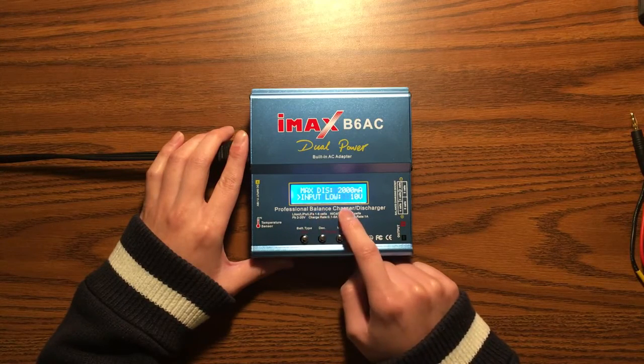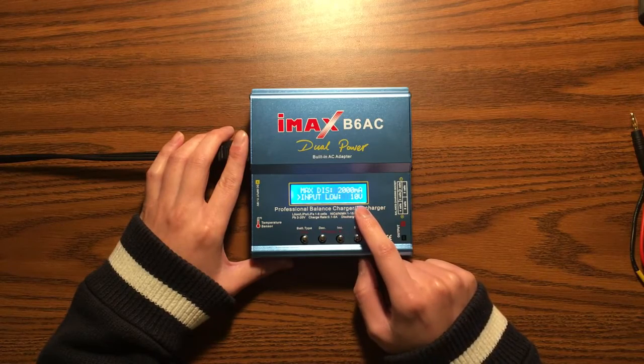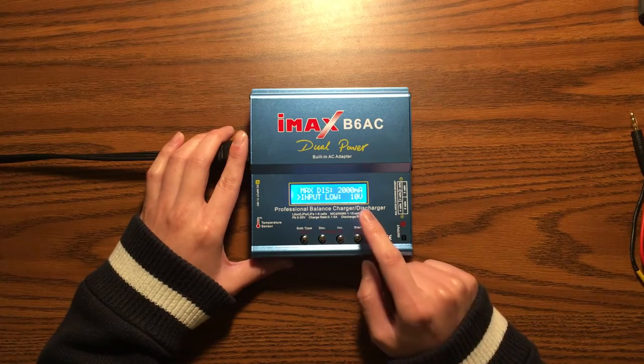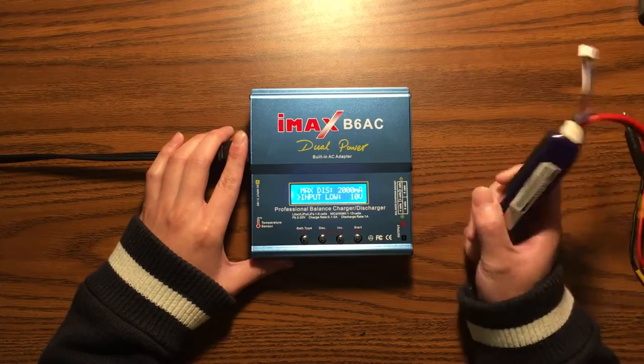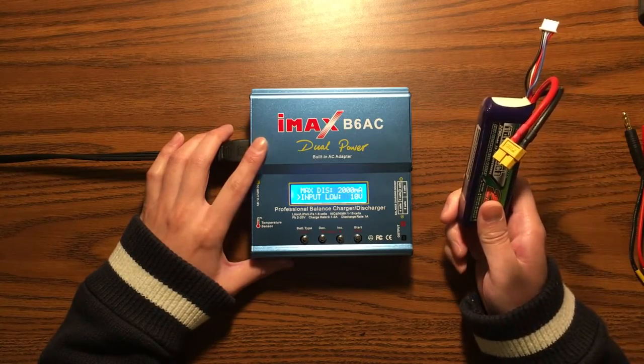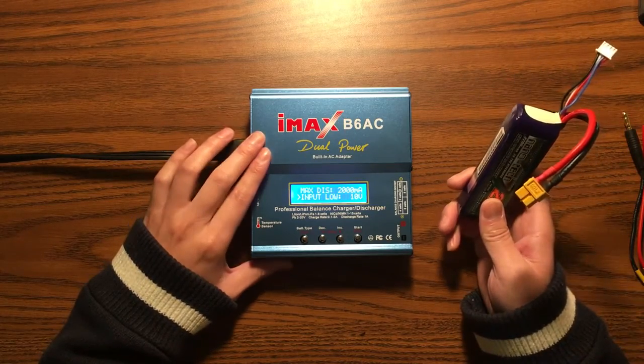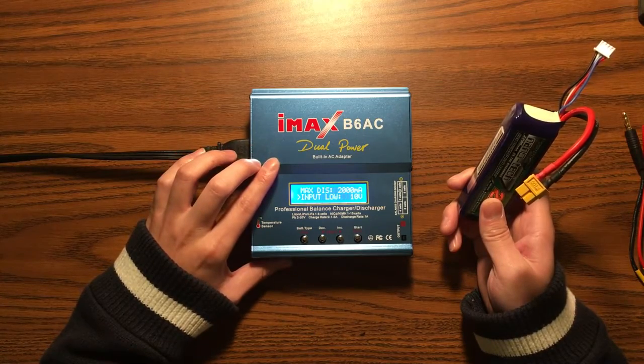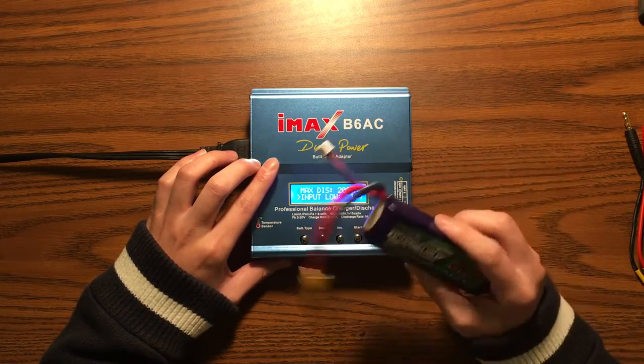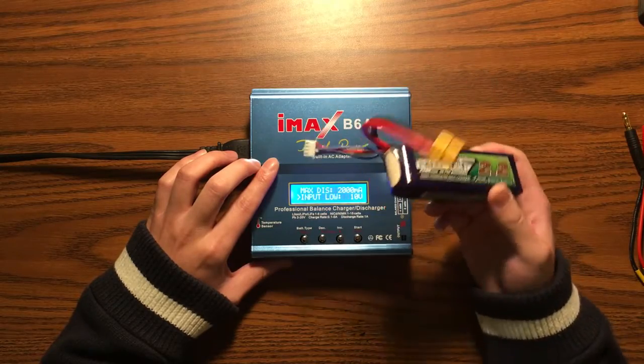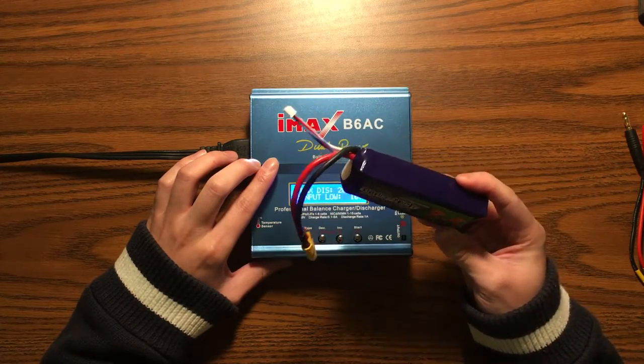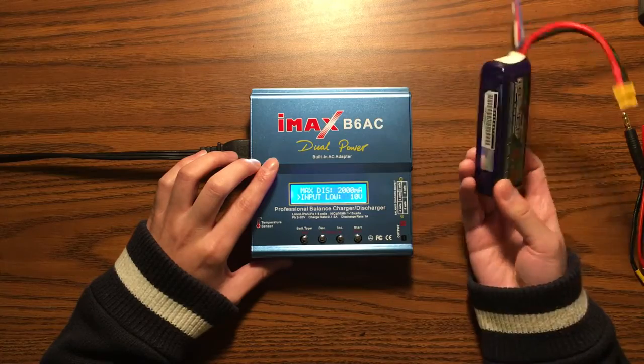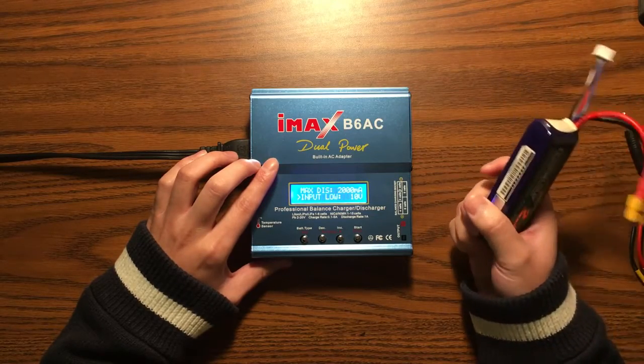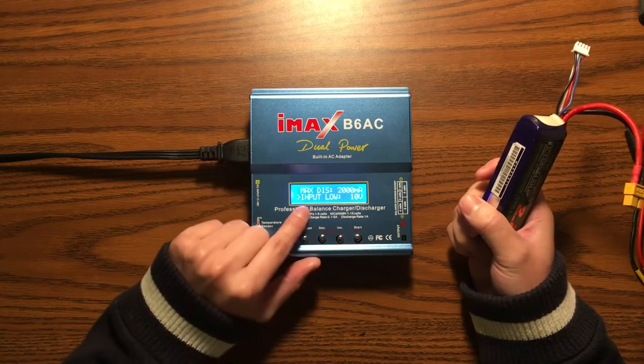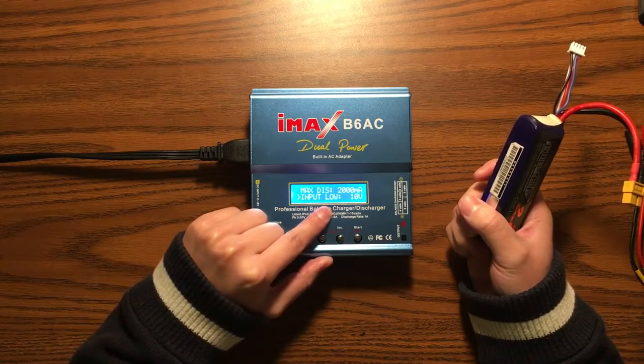The input low is the input cutoff voltage, by default set to 10. This matters when you're using a LiPo battery to power your charger, but now we're using the built-in AC adapter, so that's not a problem. If you're using external power supplies or external batteries, especially LiPo batteries, you do not want to over discharge them, so you want to set this voltage very carefully.